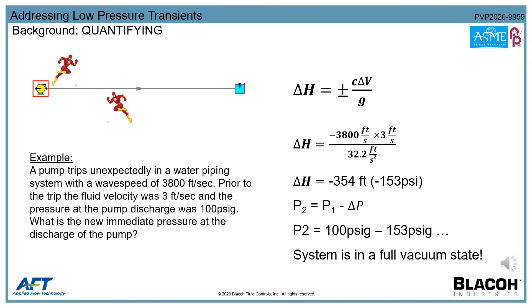What is often overlooked is that it does not take much of a change in velocity to send some fluids into a full vacuum state. In this example, water is flowing at a velocity of 3 feet per second, the system's wave speed is 3,800 feet per second, and the steady state pump discharge pressure is 100 psi. The system experiences an unexpected pump trip — and assuming no surge protection and a long wave period, the system is now in a full vacuum state.